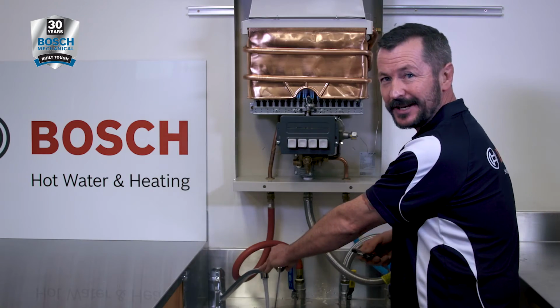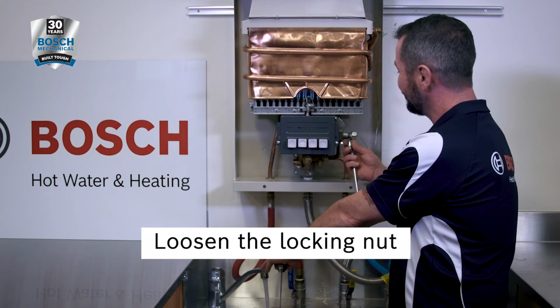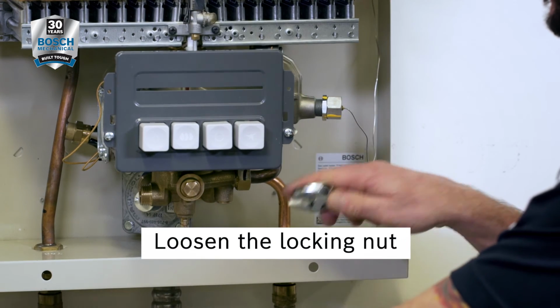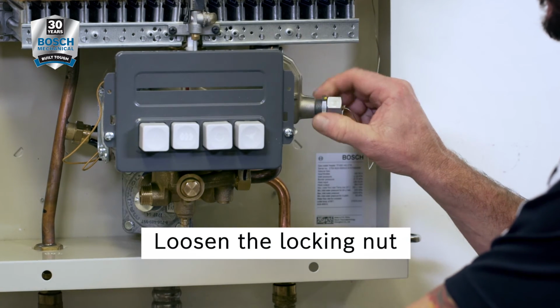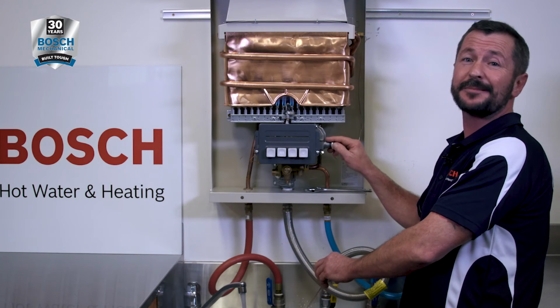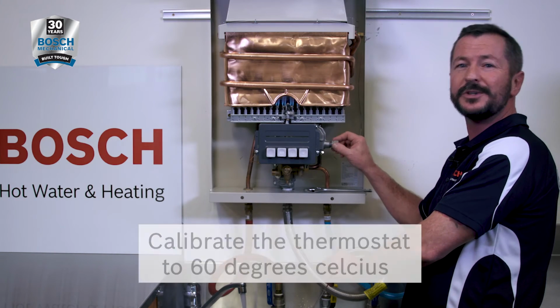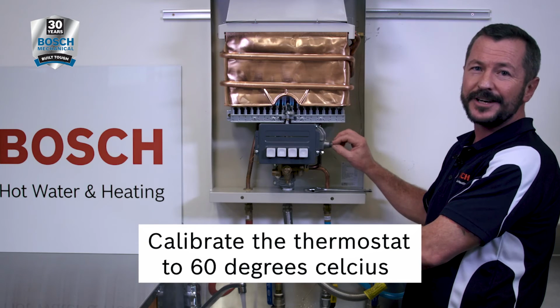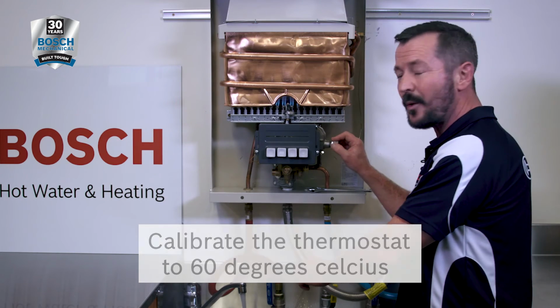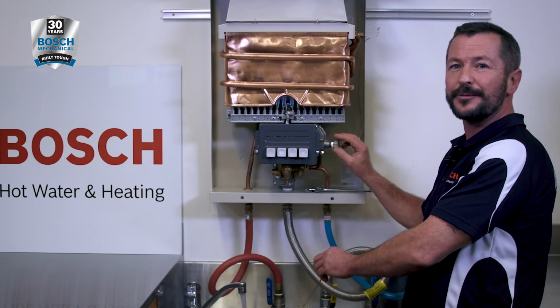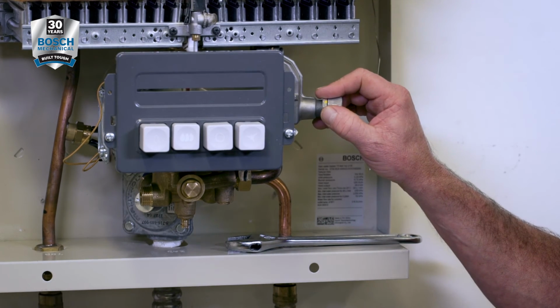To calibrate the thermostat, loosen the locking nut here. On the side of the thermostat there's a plus sign and a minus sign, which tells you which way to turn the adjustment nut to either increase or decrease the temperature. Always allow the thermostat to settle for about a minute before making further adjustments.